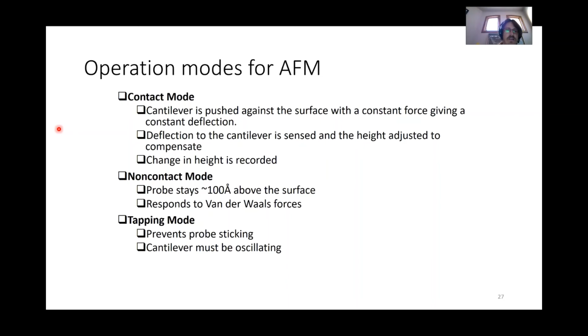Operation mode. So this is kind of the big deal for AFM. So contact mode, the cantilever is pushed against the surface with a constant force, giving constant deflection. And the deflection of the cantilever is sensed and the height is adjusted to compensate. And so that change in height is what you measure. Non-contact mode, so the probe's really close to the surface, okay? This is not tunneling because you're not applying a current to the tip, okay? So that's a big difference between AFM and scanning tunneling microscope, you're not applying a probe current in an AFM. So here, the probe is staying 100 angstroms roughly above the surface, and it's responding to van der Waals forces. So it's going to move, and that movement is detected by the laser system.